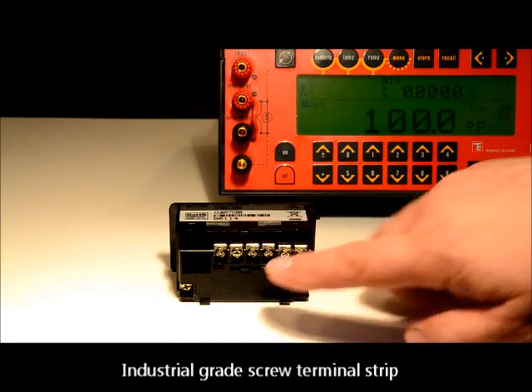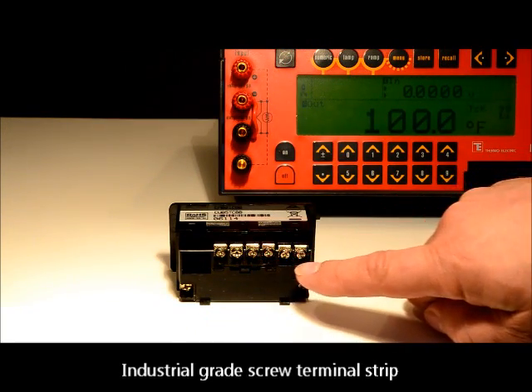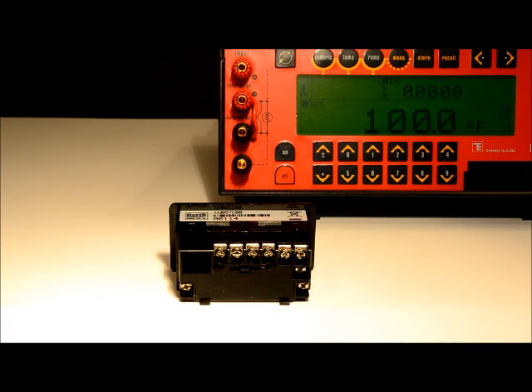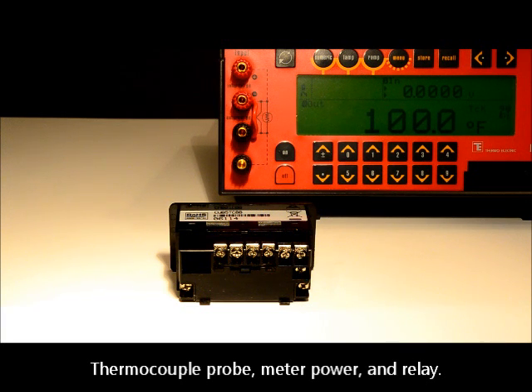At the back of the meter, we find an industrial grade screw terminal strip for securely attaching the wires to the meter. We like screw terminals since they really get a tight hold on the wires, which lessens concern over the wires vibrating loose. These connections encompass all of the meter I/O, including the thermocouple probe, meter power, and relay.